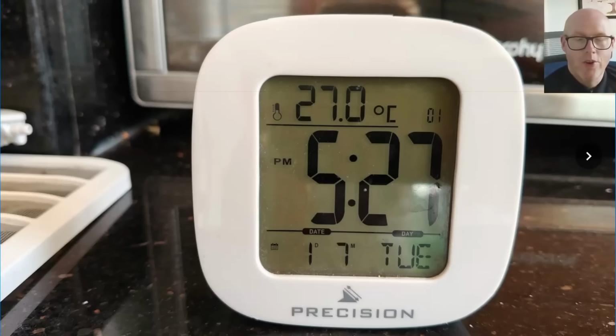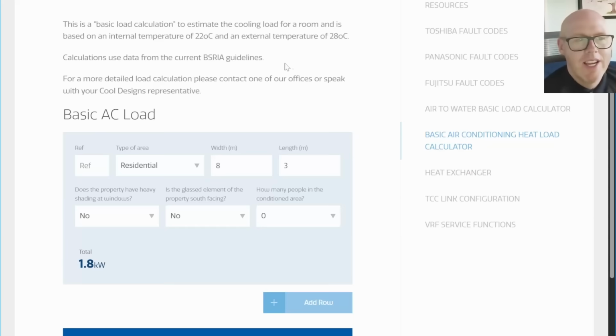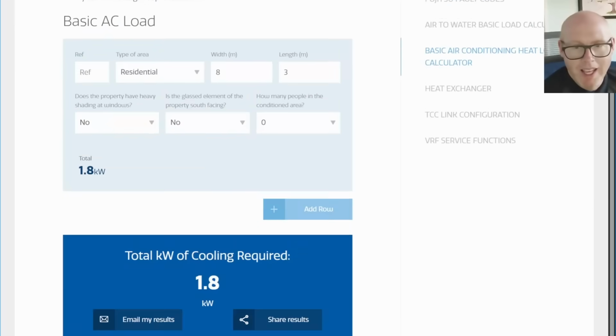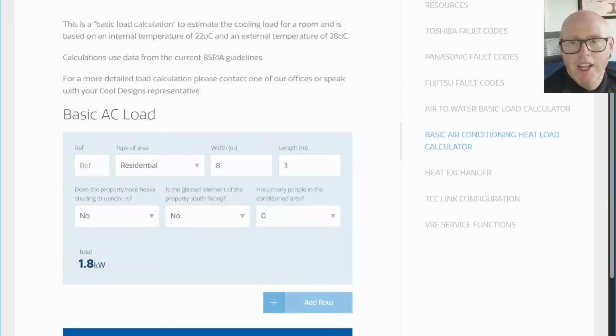Now, to calculate the cooling load and the size of the AC unit, there's loads of these basic heat load calculators and cooling calculators, and they're very basic. You can put in some basic figures, but you can't actually put in the fabric of the room, and you can't do very accurate calculations in most cases. This one, for example, says 1.8 kilowatts required if the external temperature is 28 degrees and you want an internal temperature of 22 degrees. That would be excellent if 1.8 kilowatts could actually do that.